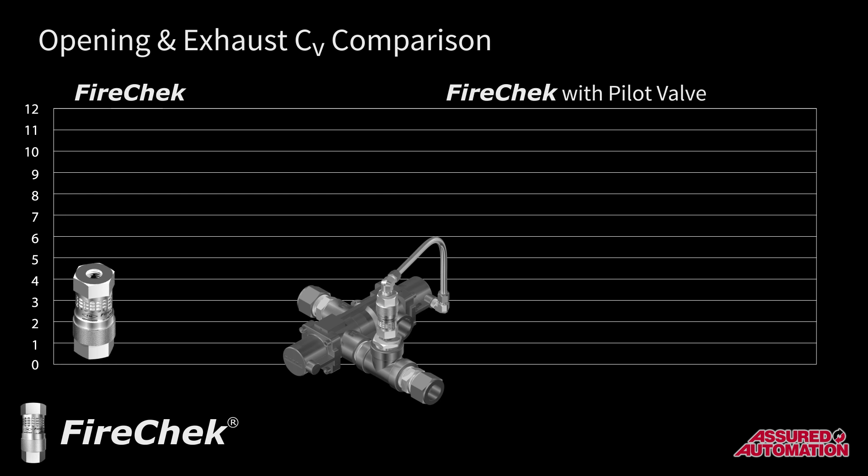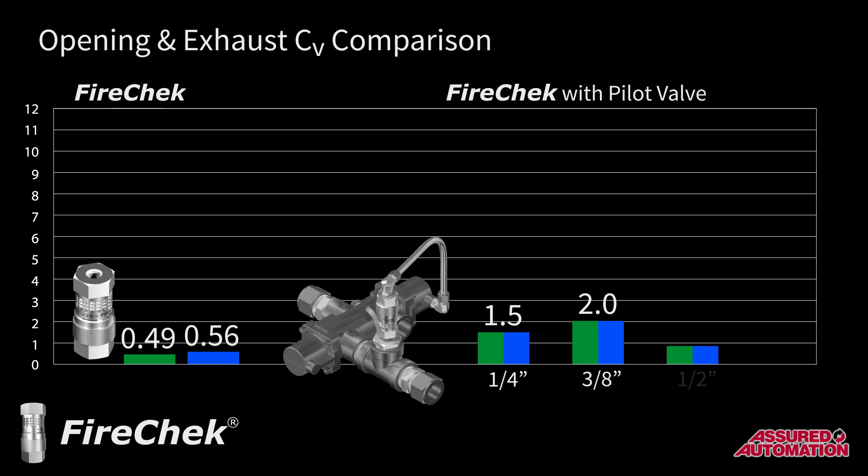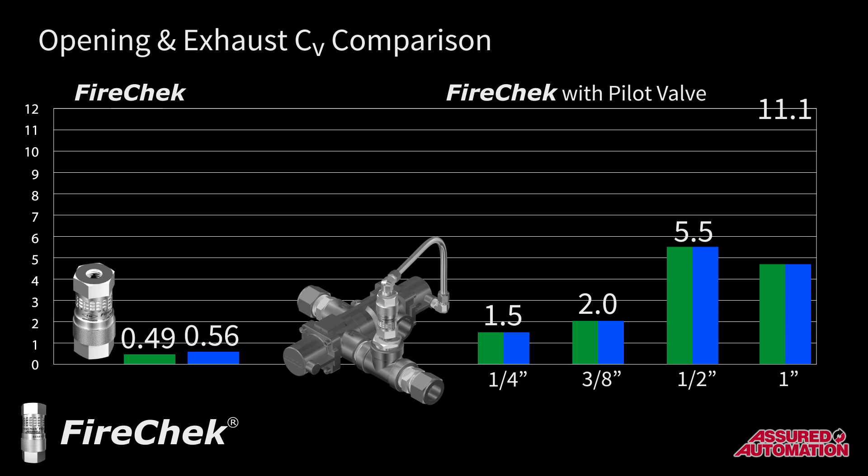These pilot valve assemblies expand the FireCheck valve's capability by increasing both the opening and exhaust CV. The CV of the FireCheck valve itself is 0.49 inlet and 0.56 exhaust. 1/4-inch pilot valves increase both values up to 1.5; 3/8-inch goes up to 2; 1/2-inch up to 5.5; and 1-inch pilot valves increase both inlet and exhaust CVs up to 11.1 — about 20 times the airflow of the FireCheck valve itself.